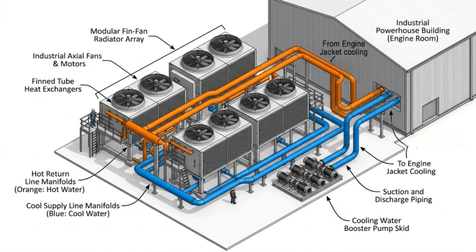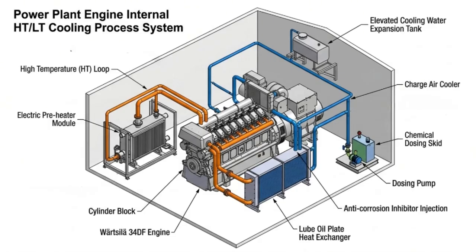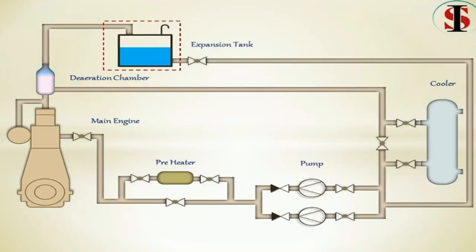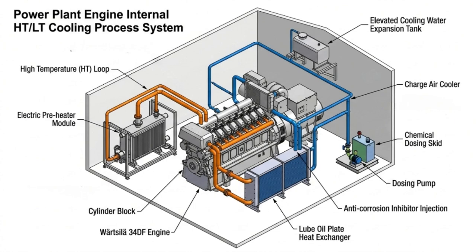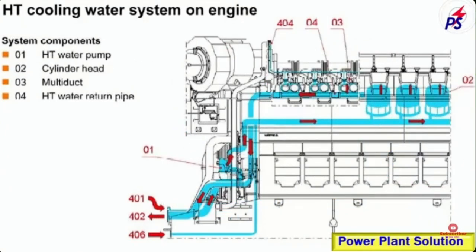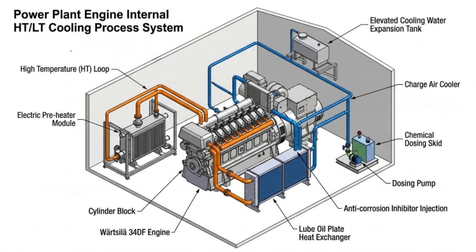Next, continuous operation of the dual-fuel engines generates significant thermal energy, requiring an efficient cooling system to maintain stable operating conditions. The plant utilizes a dual-circuit HT and LT cooling system connected to the external radiator array shown here. The high-temperature, or HT loop, removes combustion heat directly from the engine block and cylinder components before rejecting the heat through the radiator fans. In parallel, the low-temperature, or LT loop, cools supporting systems such as lube oil and charge air to maintain engine efficiency and performance. After cooling, the water is circulated back to the engine through the cooling water pump system. To maintain long-term reliability, this entire cooling network also depends on proper water treatment and quality control.